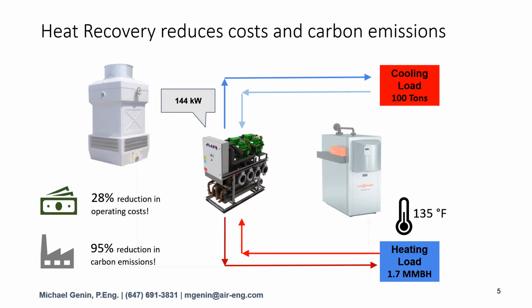This is looking at the simultaneous load only. In most buildings, there will still need to be a certain amount of excess cooling or excess heating, which cannot be derived from heat recovery. However, we've demonstrated that the simultaneous load, at least, it's more cost efficient to recover heat than it is to produce new heat, even though fossil fuels are relatively inexpensive.